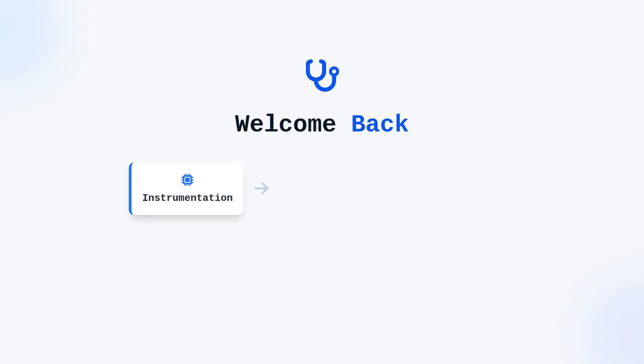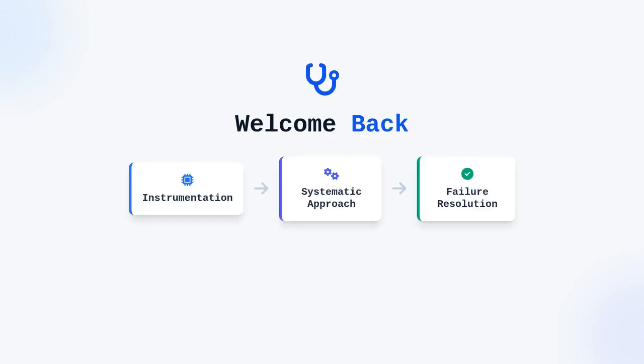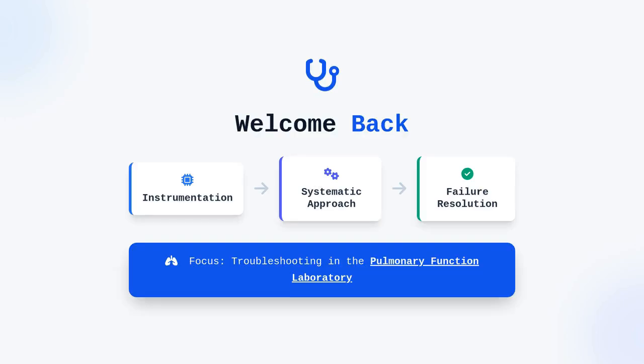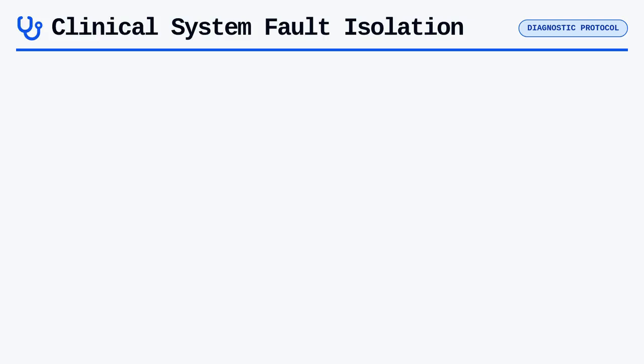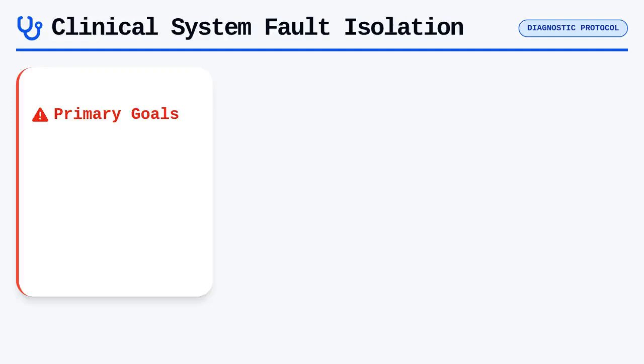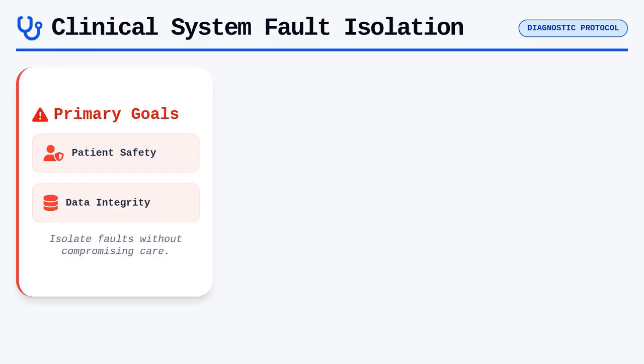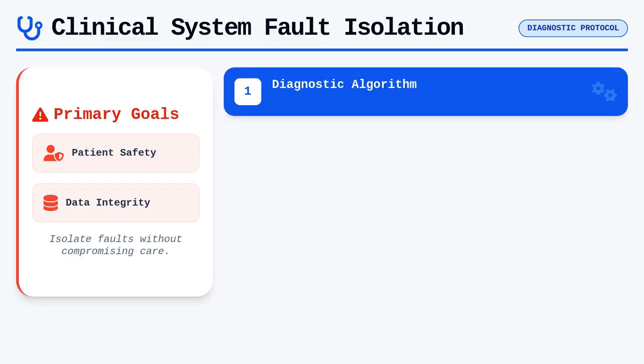Welcome back. In this lesson, we will focus on the systematic approach required to troubleshoot and resolve common instrumentation failures encountered in a pulmonary function laboratory. When a system fails under the pressure of a clinical environment, our primary goal is to isolate the fault without compromising patient safety or data integrity. You should always start by applying a diagnostic algorithm that separates hardware anomalies from software errors and calibration drift.